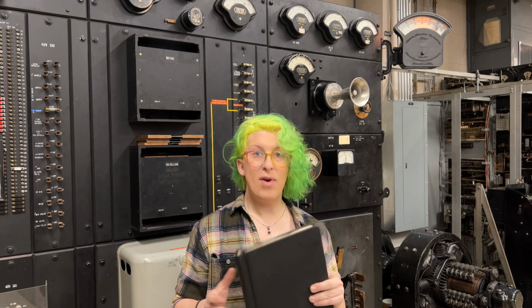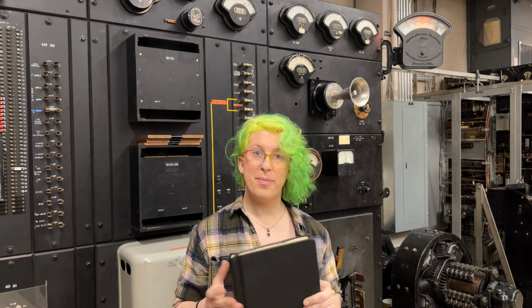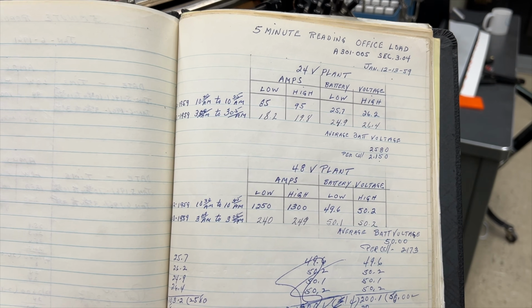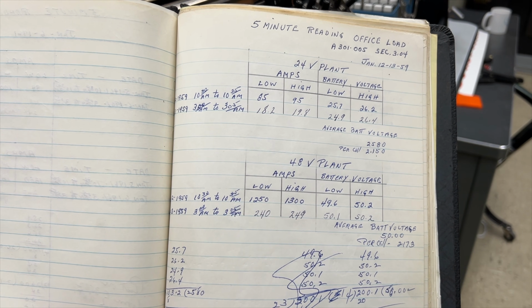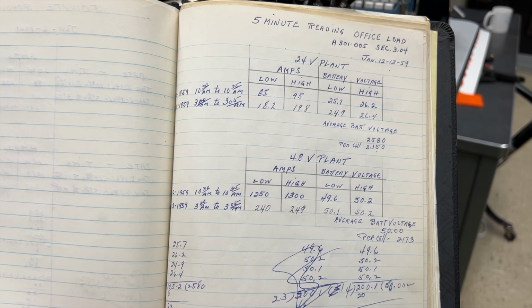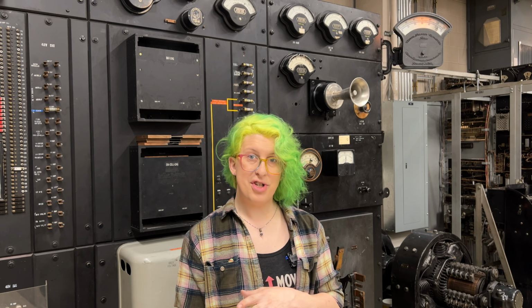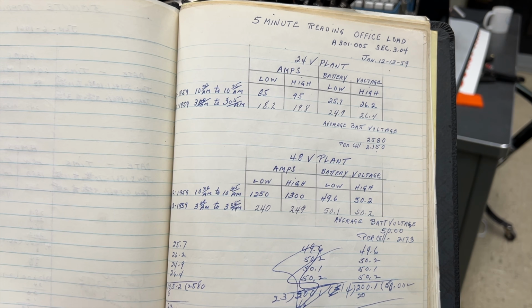We have records of the daily power usage from the Parkway office in Seattle from 1959. Here we can see the power readings were taken twice a day, once during busy hour and once overnight when the load was at its lowest, around 3 a.m. We can see that the discharge load on the 48-volt battery string at 10:30 a.m. was between 1250 and 1300 amps, and at 3 a.m. it was a paltry 240-ish amps.